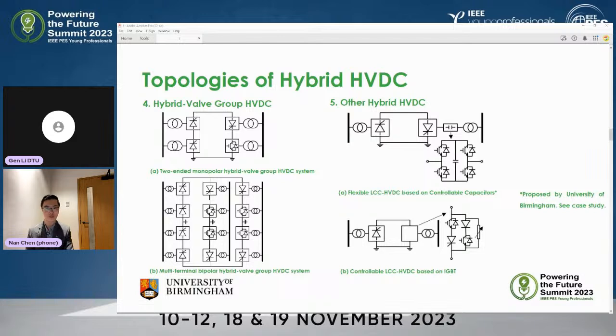The fourth topology of the hybrid HVDC is hybrid valve group HVDC, or hybrid valve HVDC. It means that no matter whether it's a bipolar or monopolar HVDC, each pole will be composed of 2 technologies. For example, an LCC and a VSC cascaded pole. For example, the 4.A. It's a 2-ended monopolar hybrid valve group HVDC. It can also be extended to bipolar, which means that both the LCC and VSC technologies can be applied to both poles.